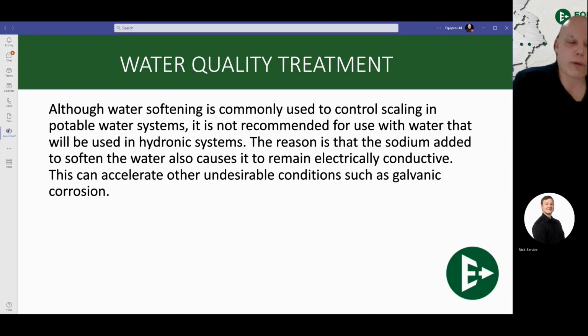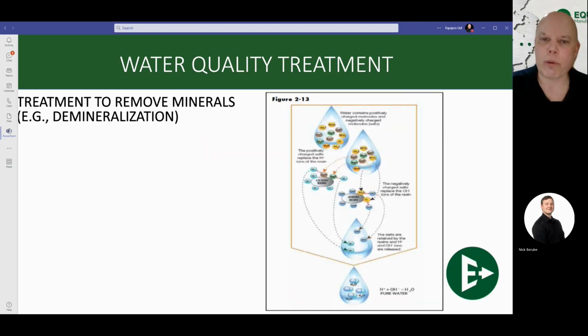So although it's softened water, the system is now extremely electrically conductive, which can lead to failure of your galvanic or galvanized components, such as the volutes of your pumps and the galvanized finishing on some heat exchangers. So softened water is not exactly the solution. Yes, it removes the magnesium and calcium, but it replaces them with something that's not as detrimental, though it can be over a long enough time. So softened water is not the best solution.